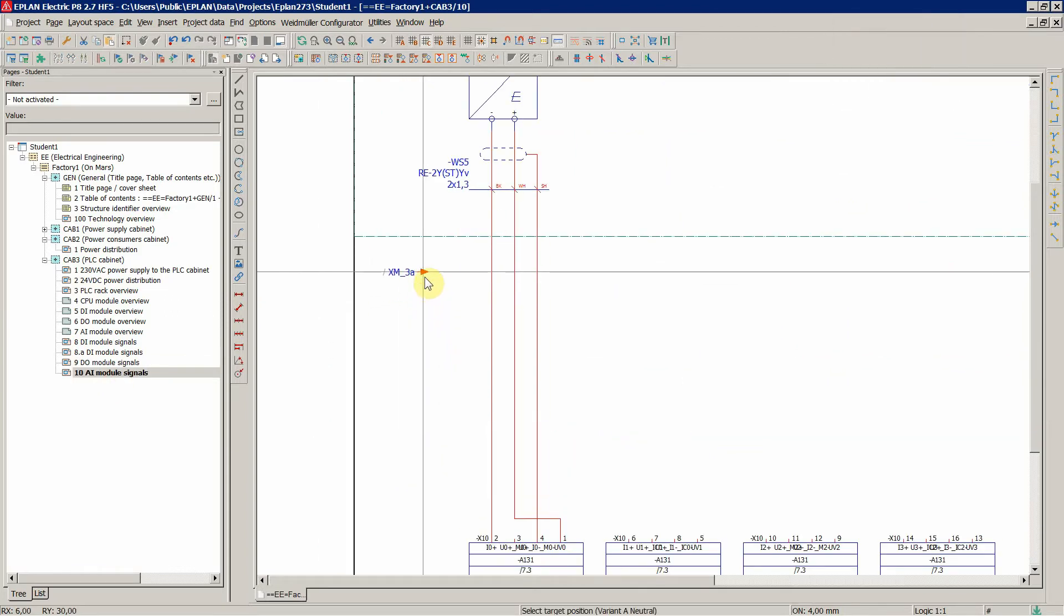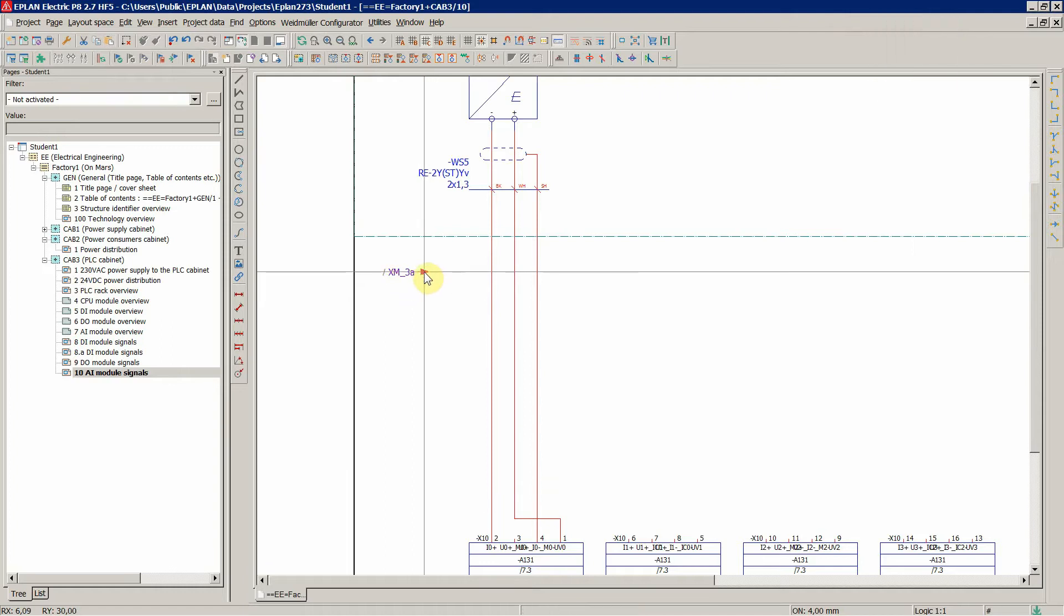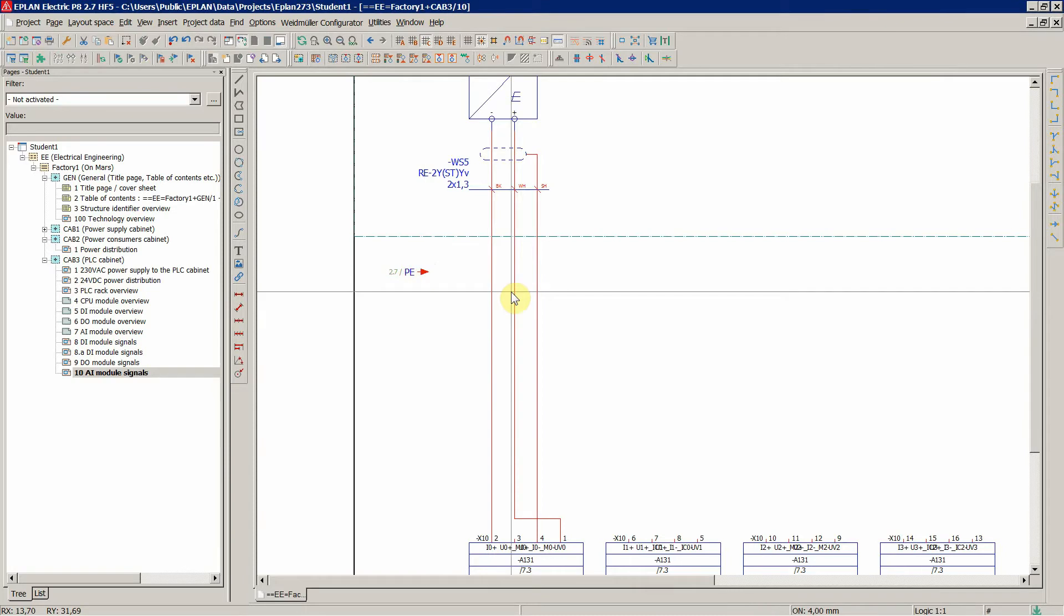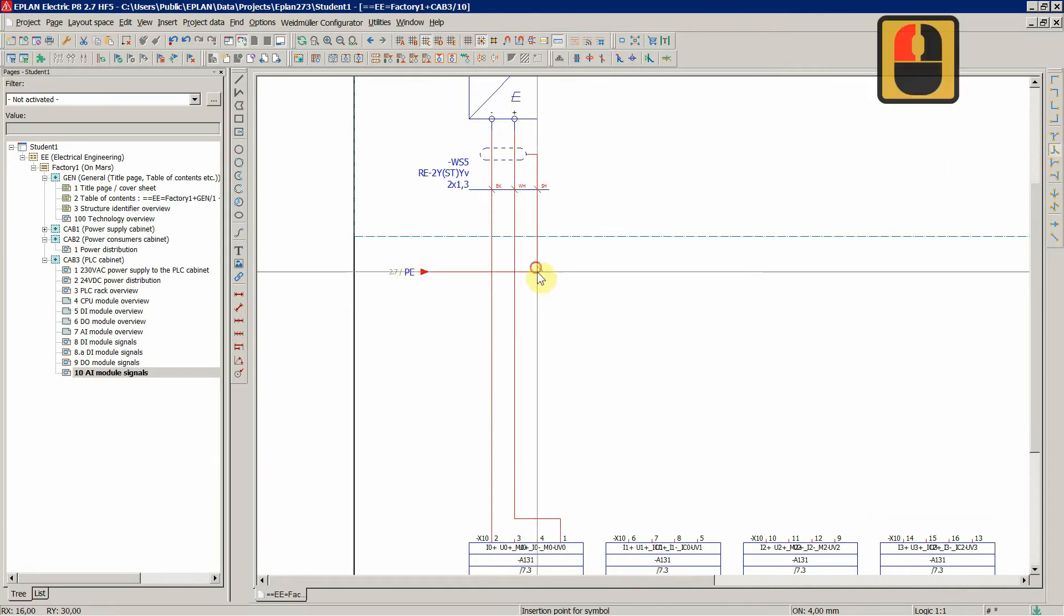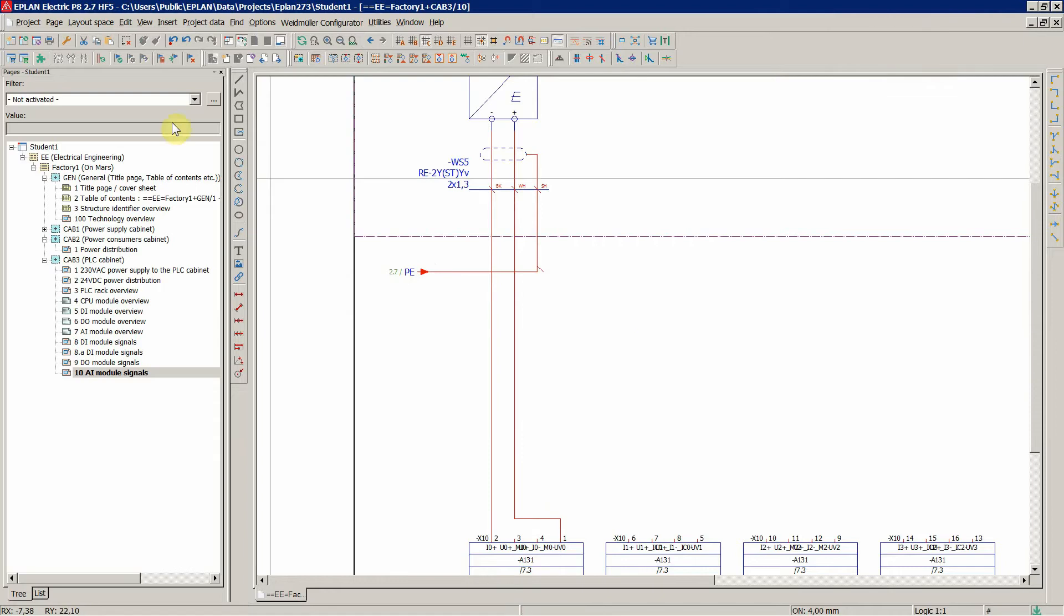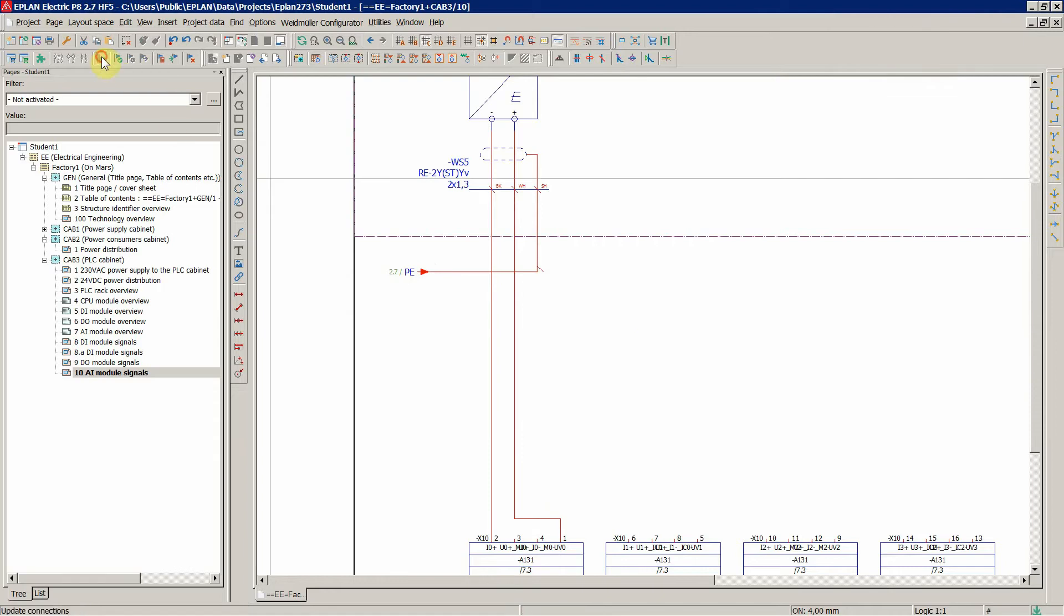As a rule of thumb, you connect the shielding of the current loops only on one side, close to the PLC. But it also depends on the application.